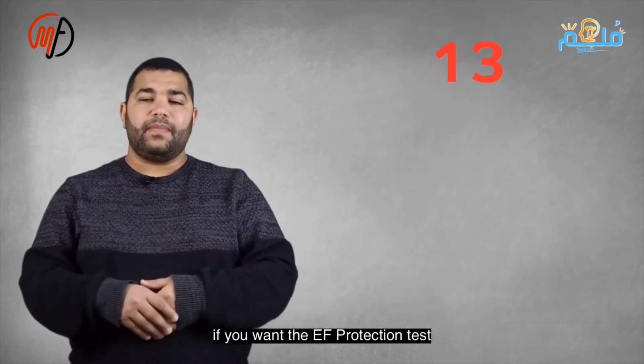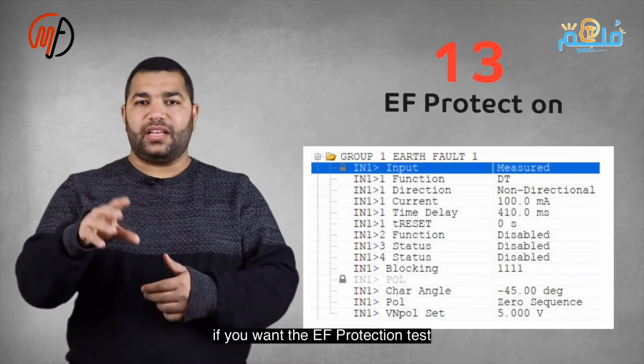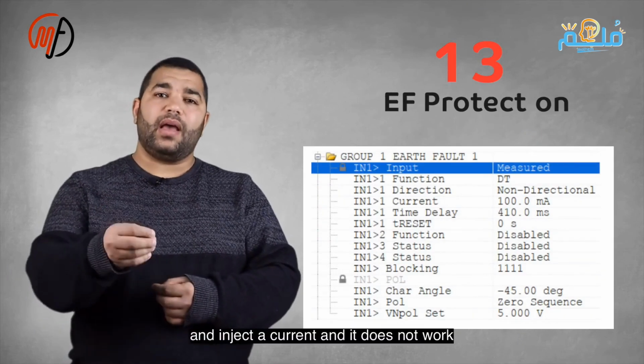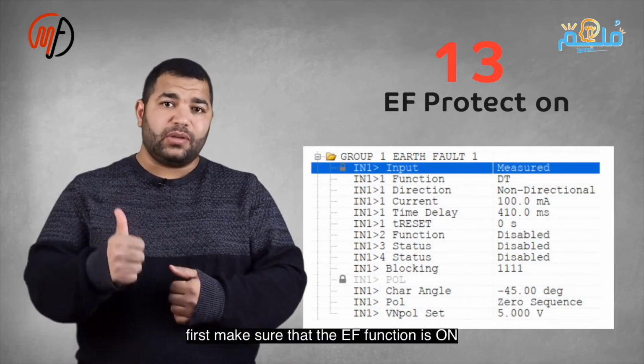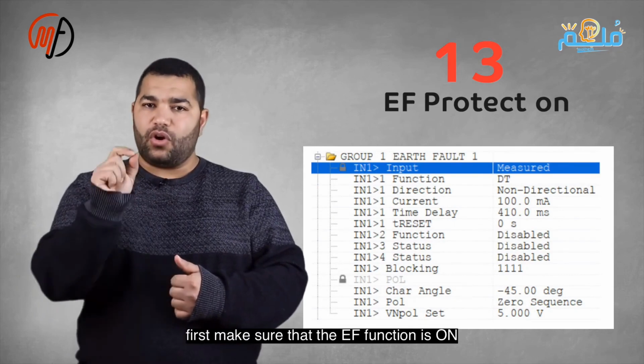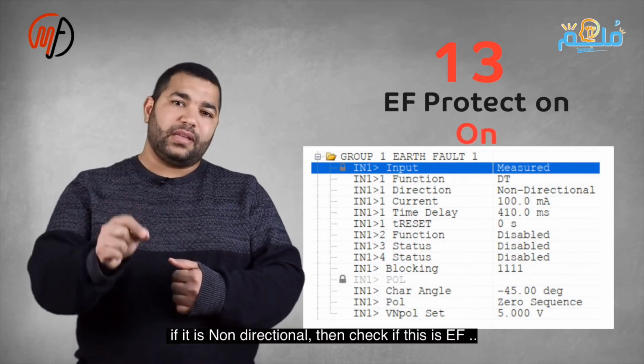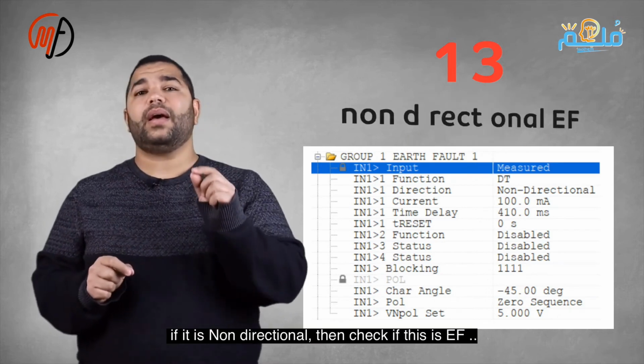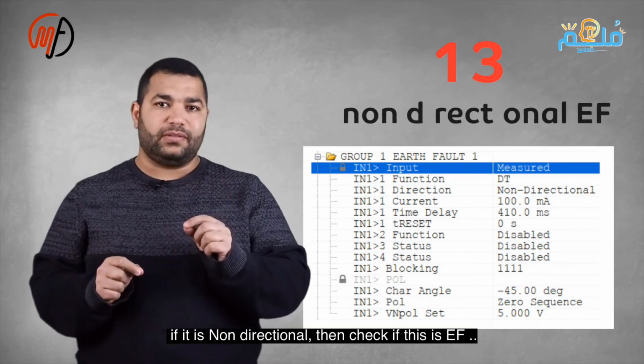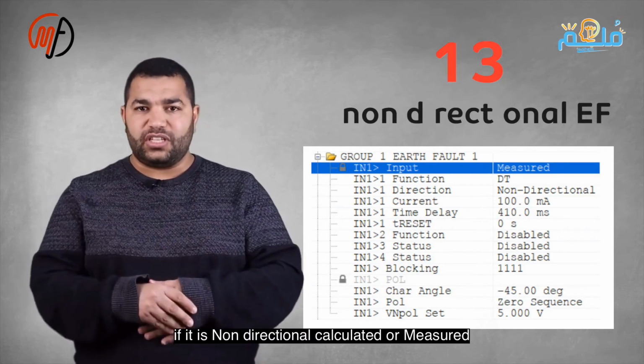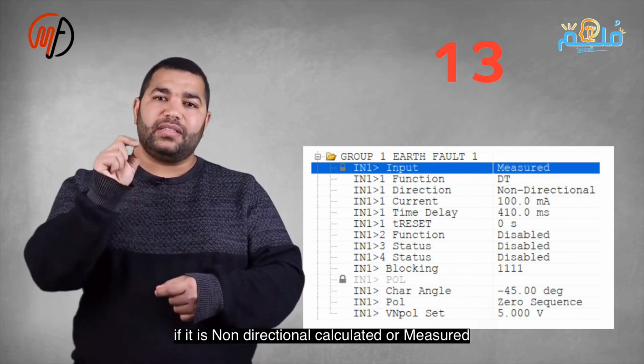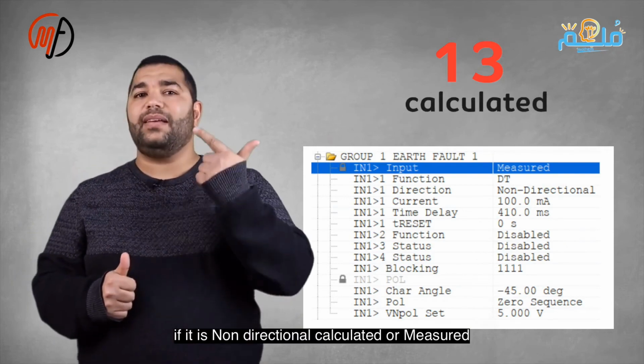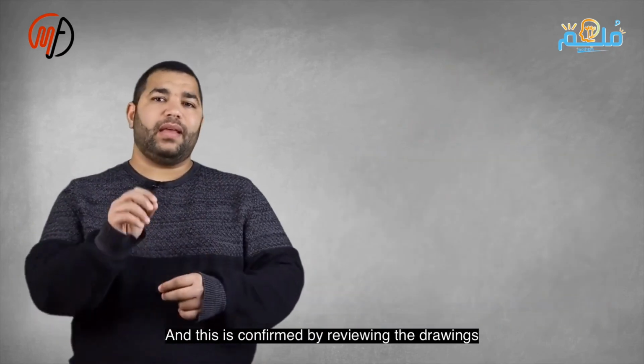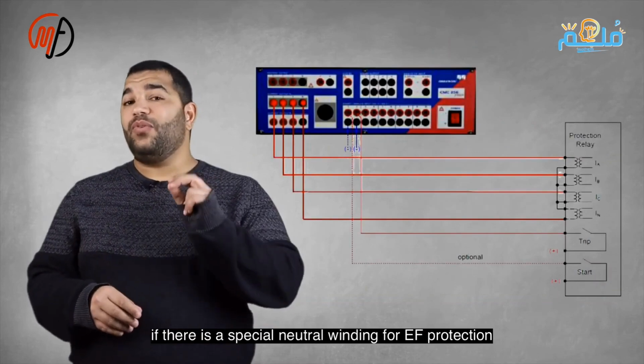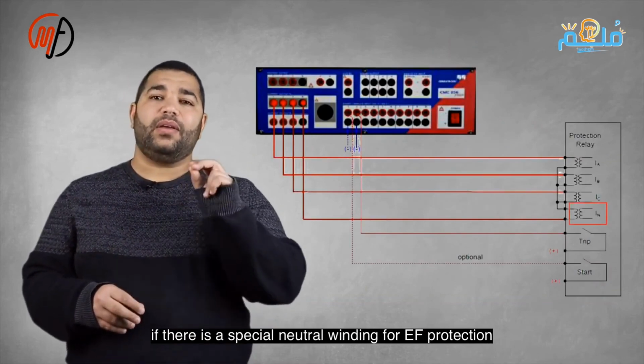13th, if you want to test the earth fault protection and you inject the current but it doesn't operate, first make sure that the earth fault protection function is on. If it is on, make sure that it is non-directional earth fault protection. If it is non-directional earth fault protection, make sure that this earth fault is calculated or measured. This is confirmed by reviewing the drawing. If there is a neutral winding specific to earth fault protection, it is a measured earth fault.